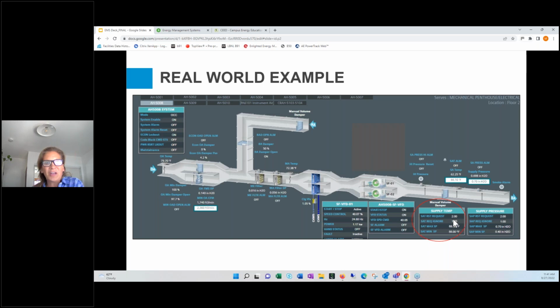So in this case, we're trying to be more sophisticated with our controls, and the results didn't quite turn out that way. And why is that? Honestly, there are a lot of different reasons. It could be that it's one IDF room or MDF room that always needs cooling and happens to be on this request list. It could be that the VAV box is just undersized, and so it's always starving and needs cooling. So there are lots of different reasons, but at the end of the day, it means that it's not performing as we want it to and saving energy. So again, if I were the commissioning agent wanting to figure out if it is working properly or not, it's quite challenging to do that, and it takes a bit of effort. Where if we had our energy management system and were able to visualize things, it might be a simpler, more efficient way of doing that.